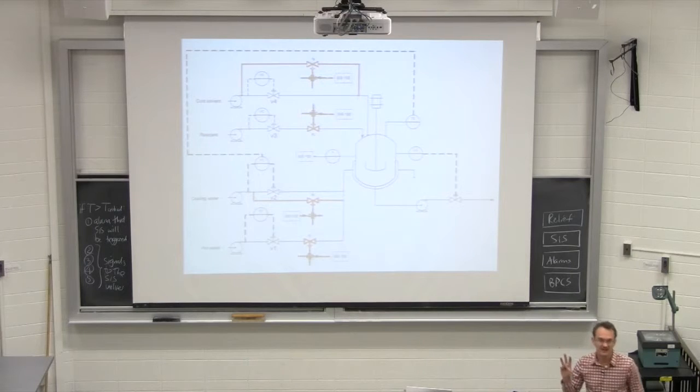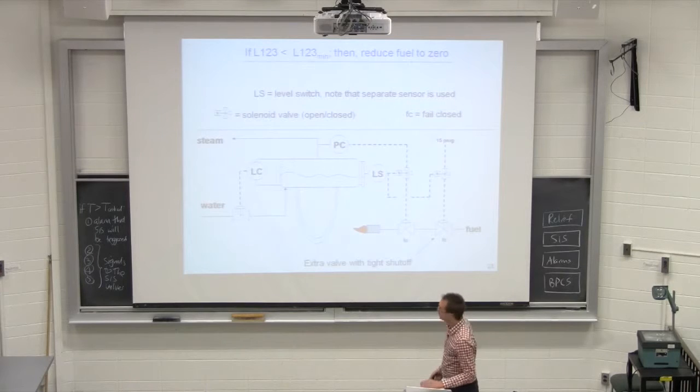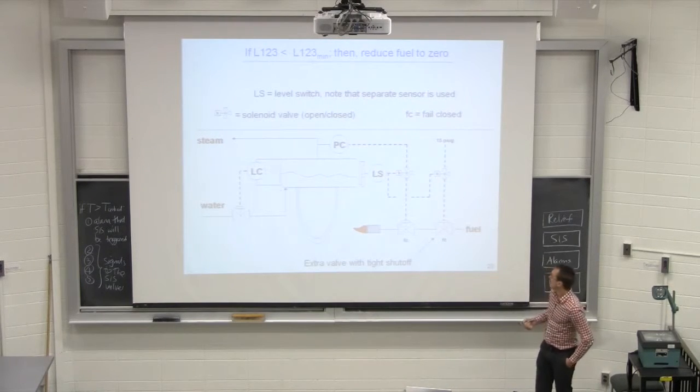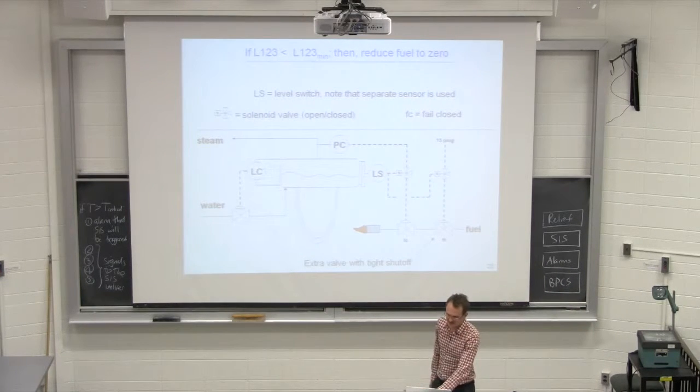If that's not clear to you, review how the solenoid valve works. We looked at that in depth in this particular example. So essentially, when SIS is triggered, that 15 PSIG pressure that we normally send, we cut that, and what we now send to the valve is atmospheric, so in other words, the valve will fail into its natural position, fail closed. We're using a mechanical process that doesn't rely on us sending a signal to the valve to close. We're going to let the valve fail closed.